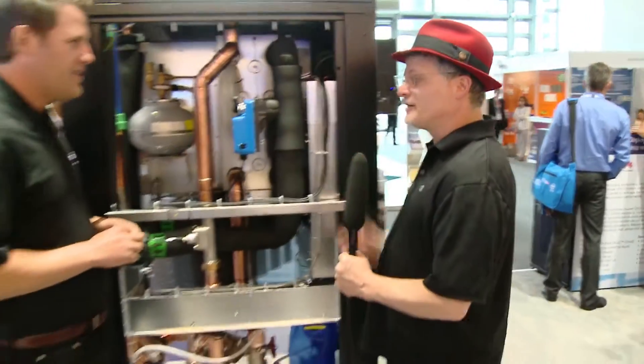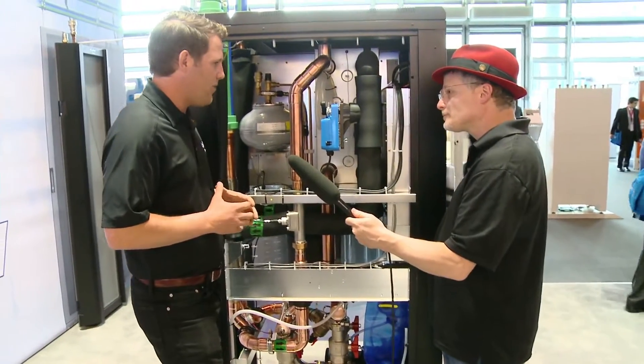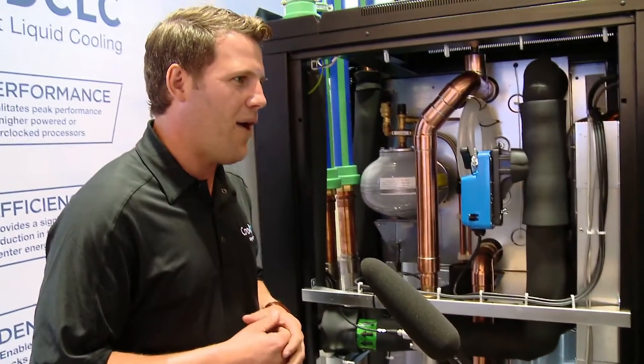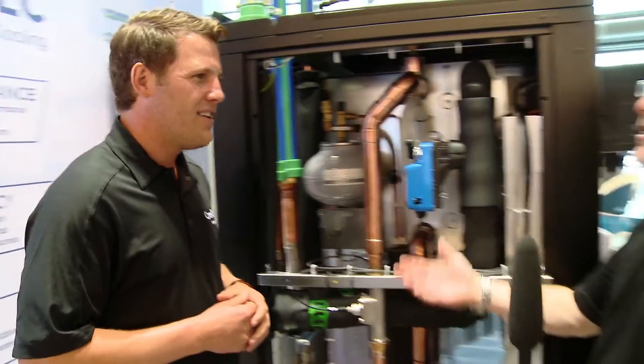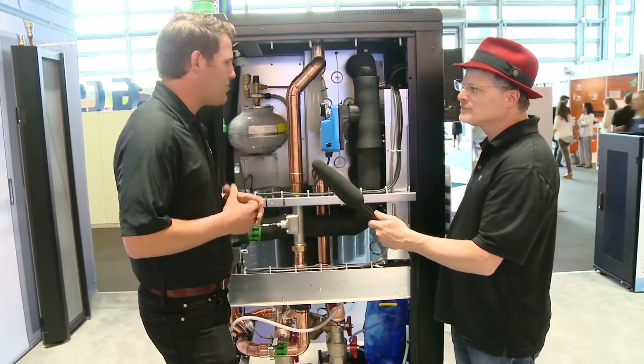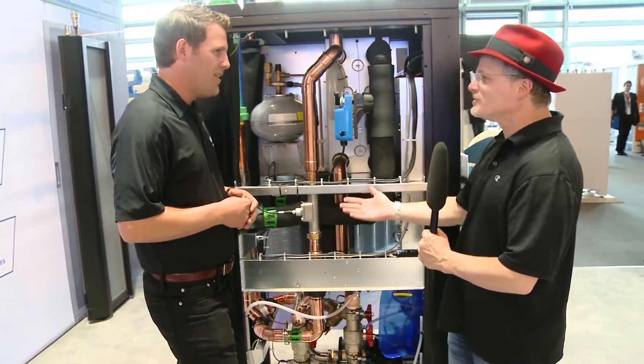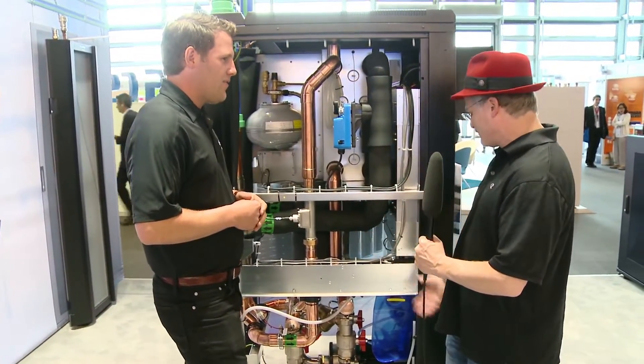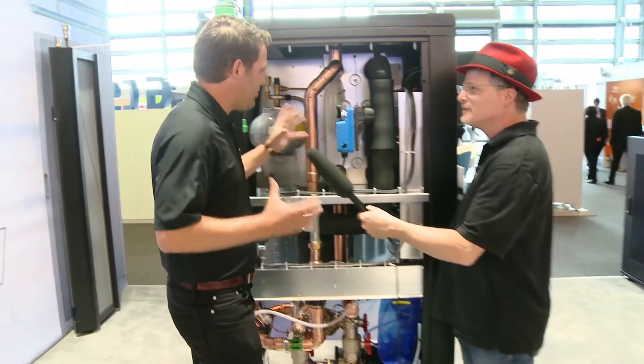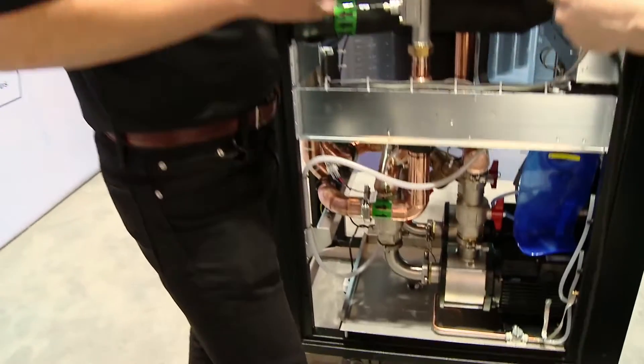Here we have the large-scale heat exchanger. It works similarly to the 2U CHX40 but, being the CHX650, it manages 650 kilowatts of power. To put that in perspective, that's roughly about 700 nodes being managed by one heat exchanger. The exact same principles are at play, and much of the same functionality exists in this system as in the CHX40. Because it's not moved as easily, it has more service capabilities in terms of being maintained in the space it occupies.